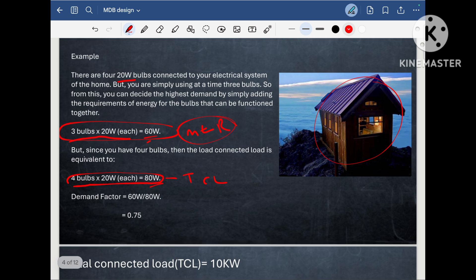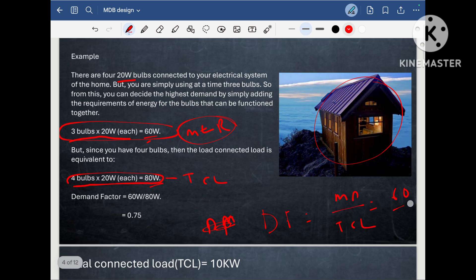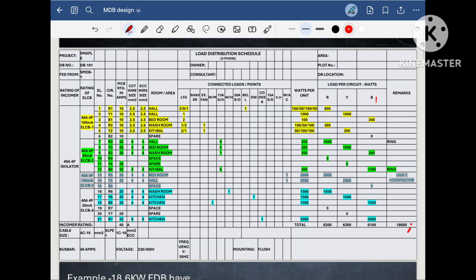So the maximum demand is 60 Watt. What is the demand factor? Demand factor is equal to maximum demand divided by total connected load, so it is 60 Watt divided by 80, which comes to 0.75. With these two examples, I hope you are very clear with the demand factor.